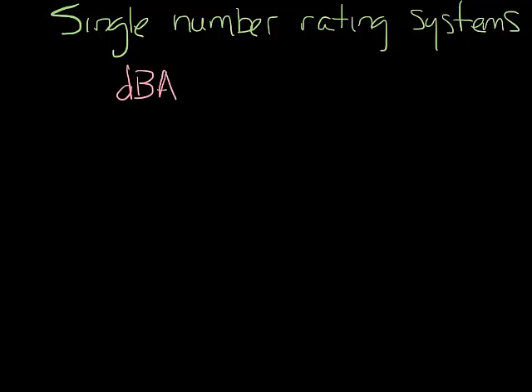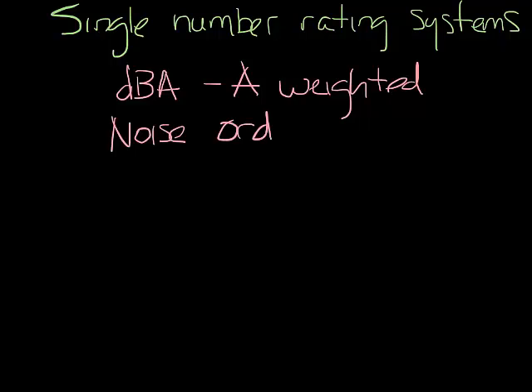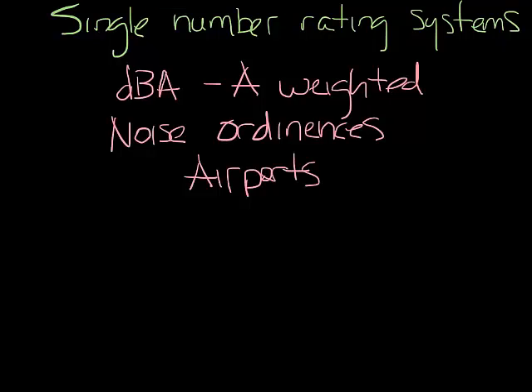DBA is probably one of the most common single number rating systems. DBA is basically a weighted scale that gives less weight to the very high and very low frequencies. It's typically used for noise conservation and outdoor noise evaluation. Think things like noise ordinances for airports. Many inexpensive sound meters give DBA readings.